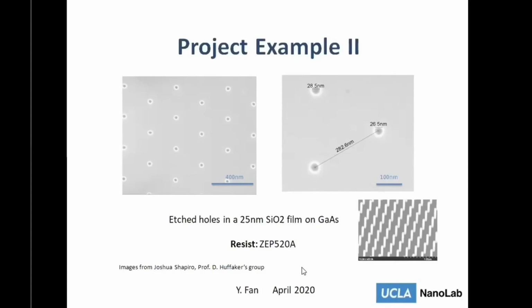Hi. For the stitching errors, do you have some common knowledge for how to avoid stitching errors? Oh, the stitching errors, there's actually two sides. One is from the tool side, right? Another is from the fracture side. From the tool side, sure, the drift might be the most important if you really think about the stitching effect.